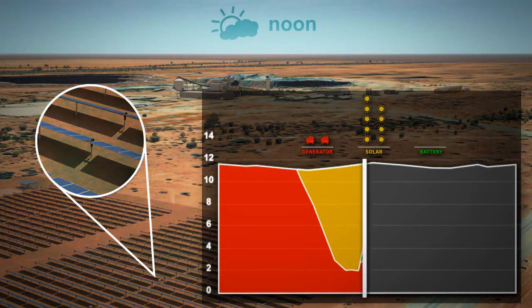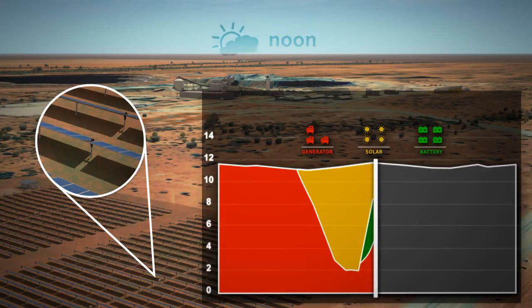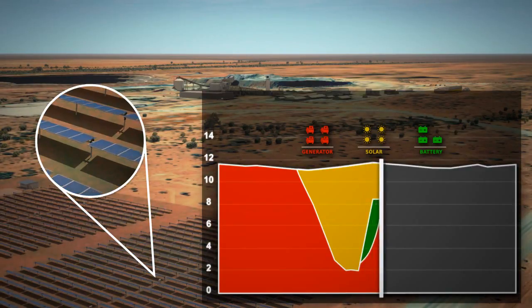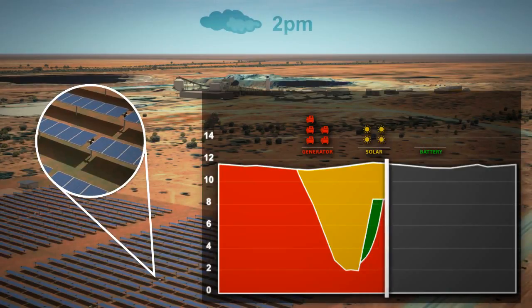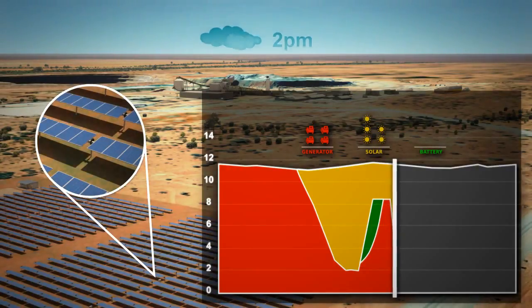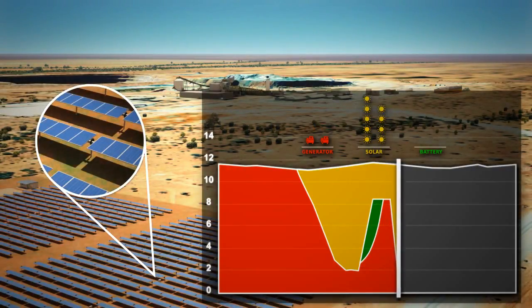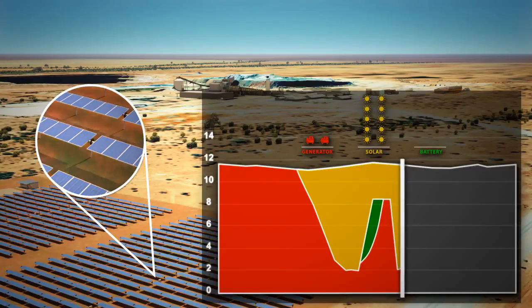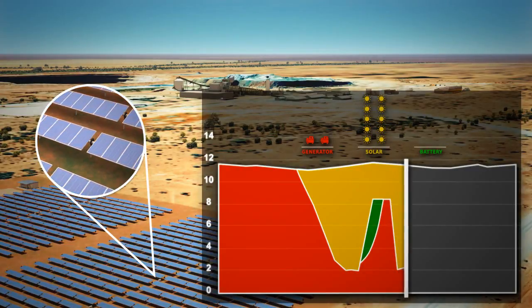When a cloud event occurs, a portion of the energy demand is taken by the reserve diesel capacity already online, with the battery able to meet the balance of demand until new diesel generators can be started and brought online. Once the cloud passes, the power station reverts back to solar power and turns off the diesel generators, which are no longer needed for the time being.